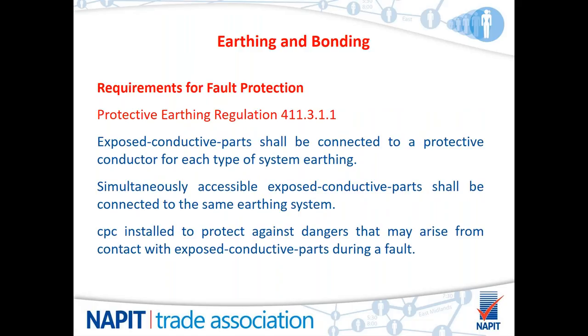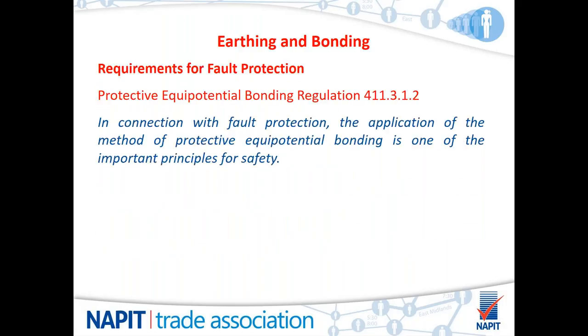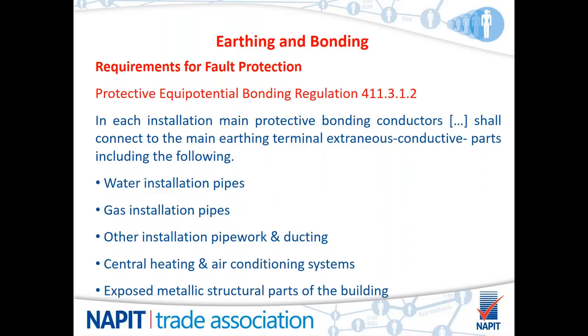So, the requirements for fault protection. Protective earthing, regulation 411.3.1.1, states that exposed conductive parts shall be connected to a protective conductor for each type of system earthing. Simultaneously, accessible exposed conductive parts shall be connected to the same earthing system, and a CPC installed to protect against dangers that may arise from contact with exposed conductive parts during a fault. That's earthing. Bonding is also important. In connection with the fault protection mentioned, the application of the method of protective equipotential bonding is one of the important principles for safety.